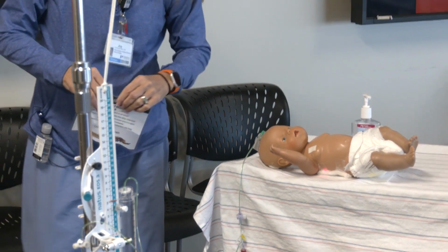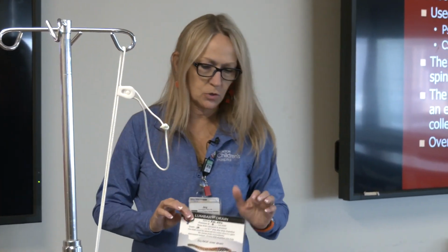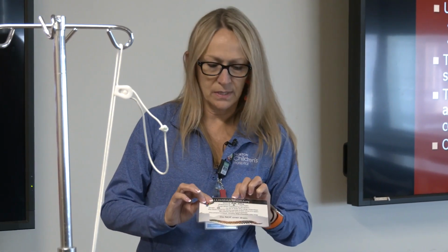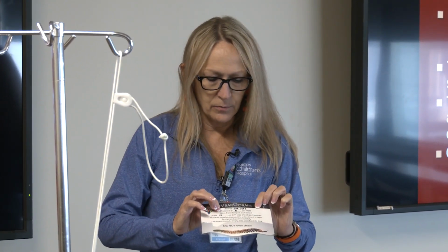It has been written before as 0 to the umbilicus. If it is, you just point the laser light at the belly button. But in general, it'll say externalization site. And there's also a line for the pressure. It's not a level, remember, what pressure is this going to be set at? So there's a number. This one says 5 centimeters of water.